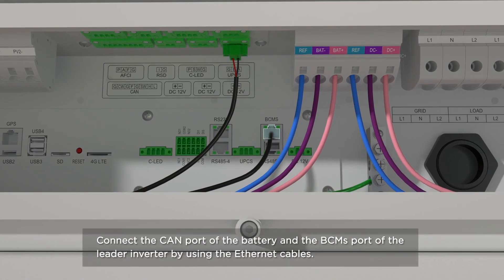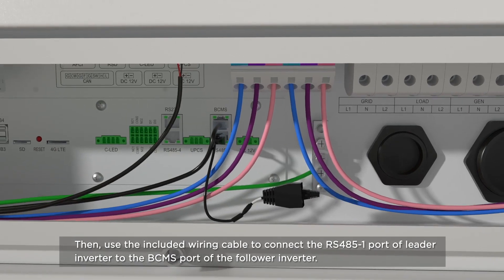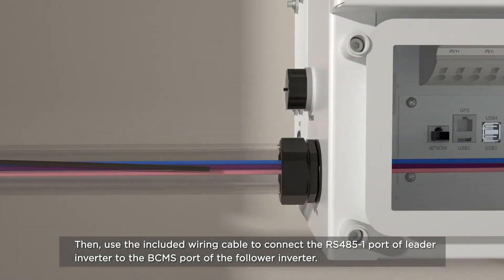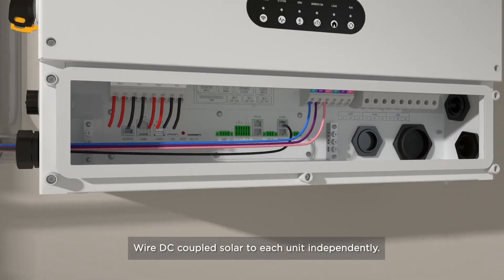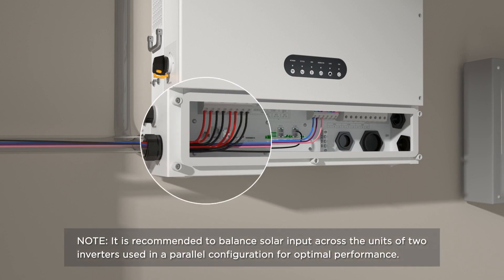Connect the CAN port of the battery and BC-MS of the leader inverter using the Ethernet cables included in the PS20 package kit. Then, use the included wiring adapter and standard cable to wire the leader to the follower. Wire DC-coupled solar to each unit independently. It is recommended to balance solar input across the units of two inverters used in a parallel configuration for optimal performance.